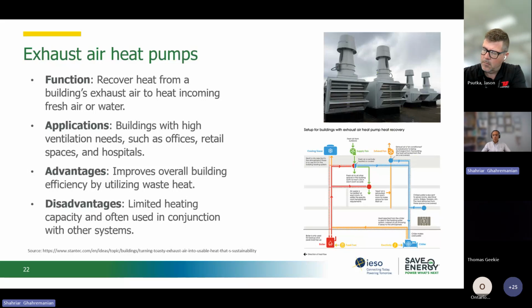So basically, we are going to utilize the waste heat that the building has, and it improves the overall building's efficiency. The only limitation is the heating capacity, because it depends on the size of the exhaust that we have. So it can be a limited amount of heating provided. But again, this heat pump is really good to be considered for any energy recovery for our buildings if we have a large amount of exhaust air going out of our buildings.